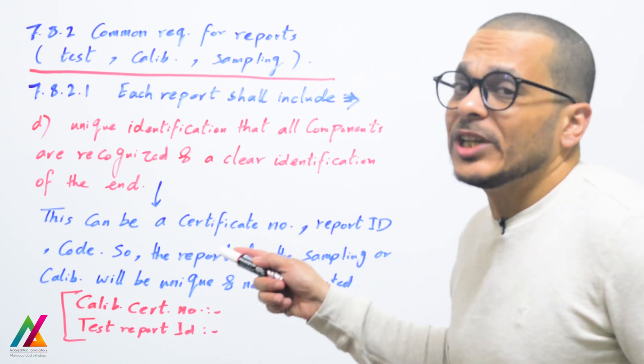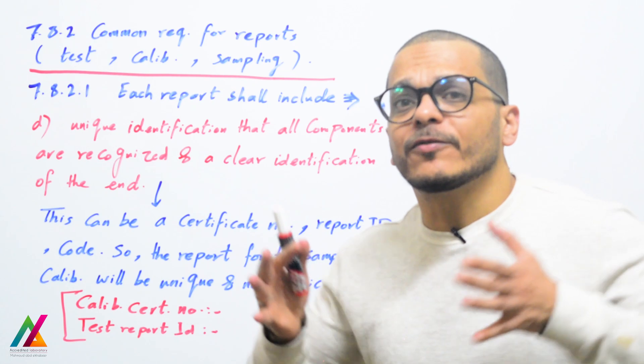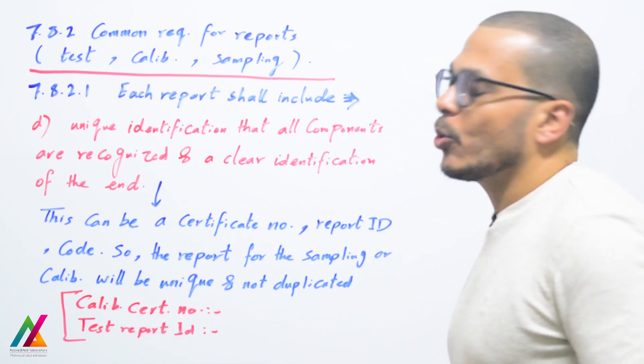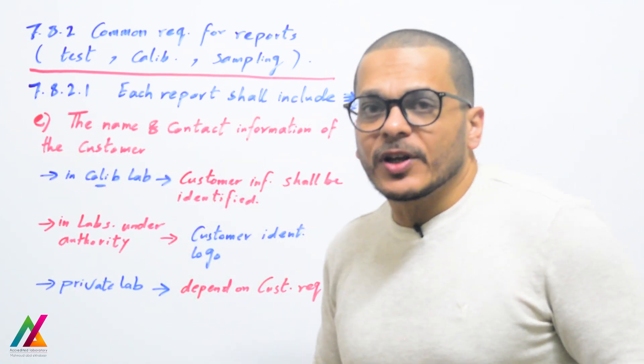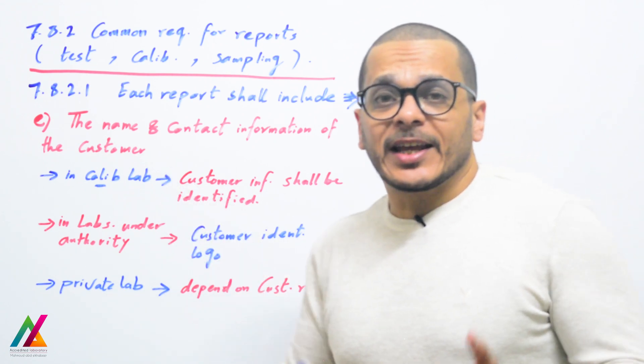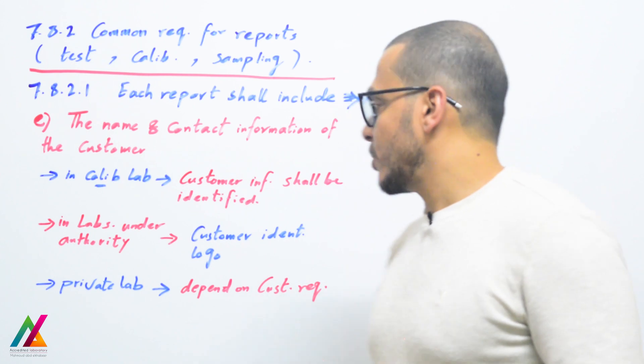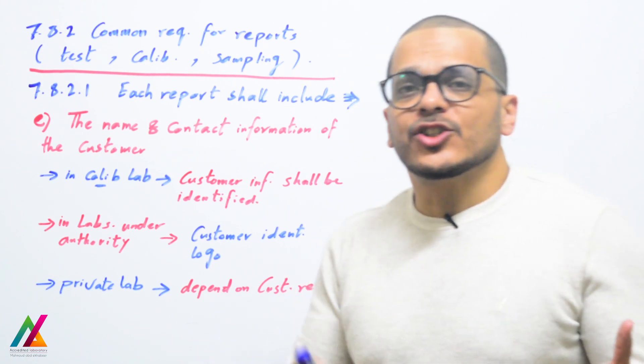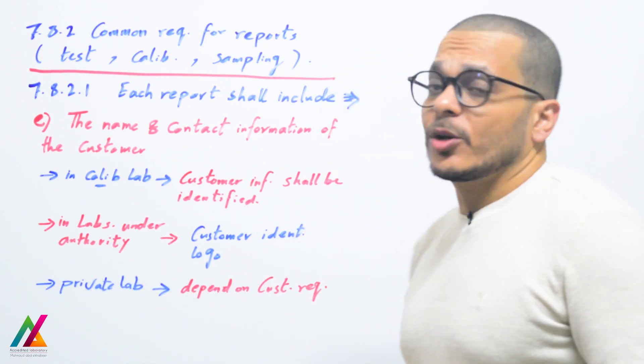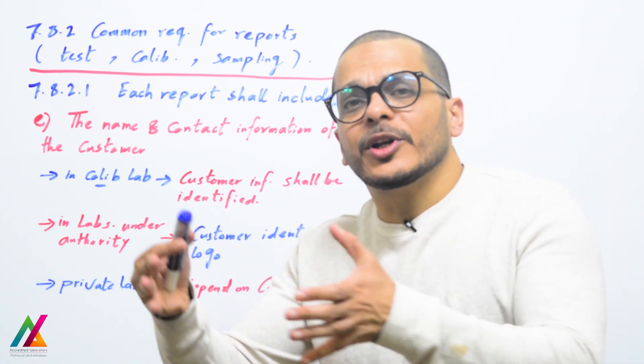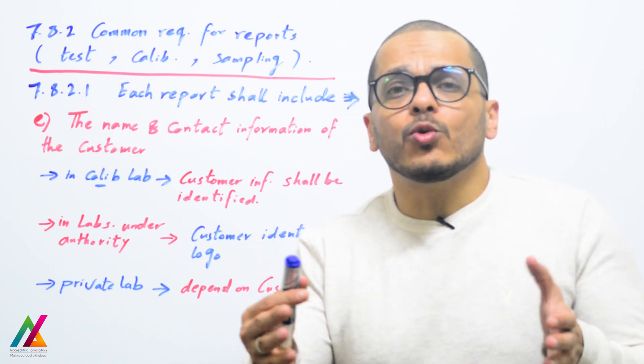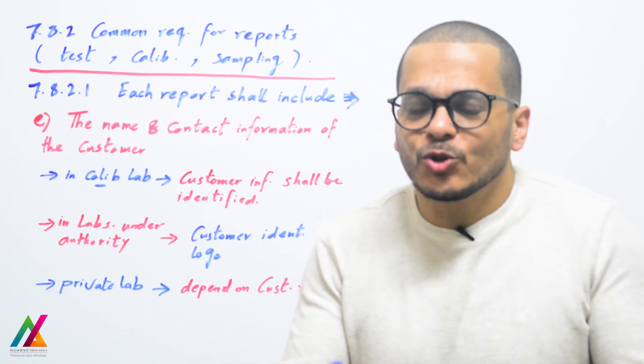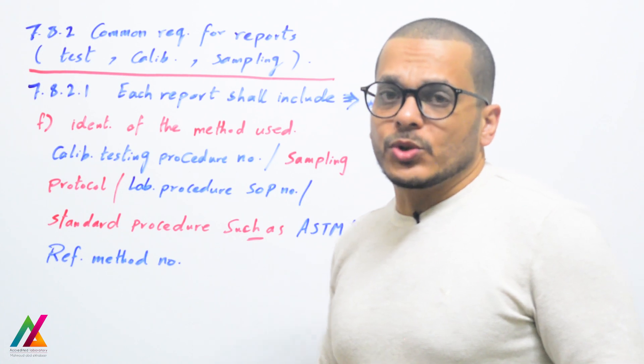The report number shall be unique for each report or sample — not duplicated. This applies to a calibration certificate number or test report ID. The name and contact information of the customer shall also be included. In a calibration laboratory, the calibration certificate shall include information about the customer. Customer information should identify the organization, company, or government authority. In a private lab this depends on customer requirements, but it is better to include it.